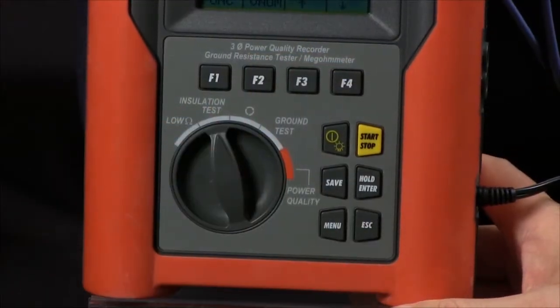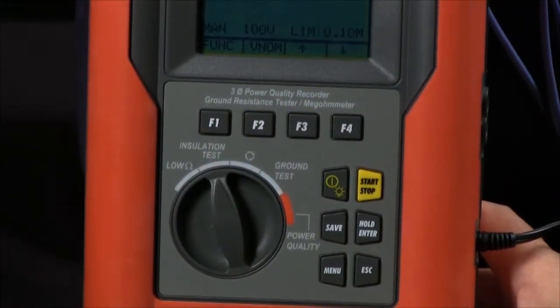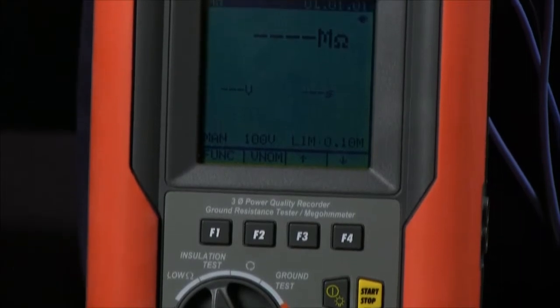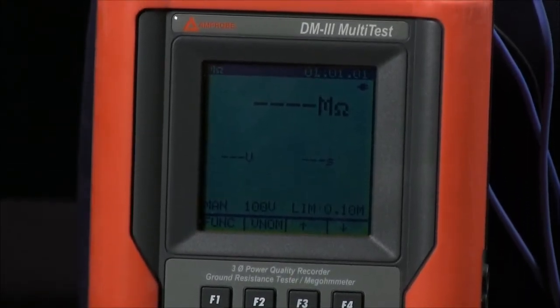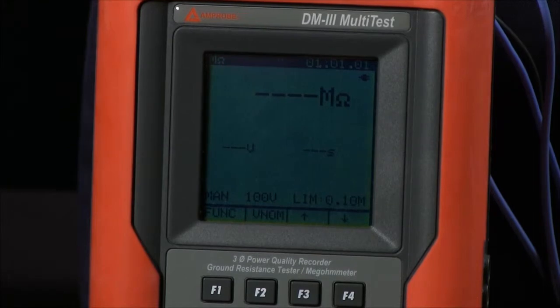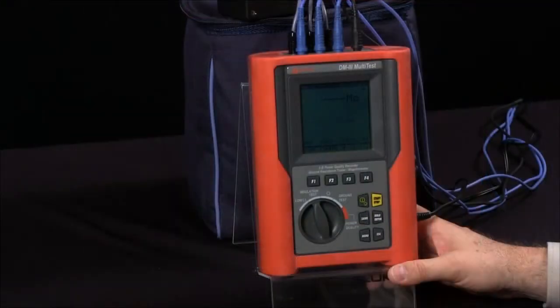I can also shift over to my insulation test, and I can range from 50 volts up to 1,000 volts of test voltage in specific increments, thereby also checking my insulation as well as my motor windings.